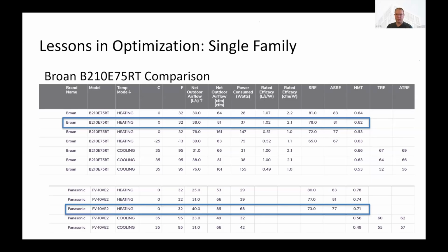Although there is a trade-off there. It has a little less heat or less moisture recovery than the Panasonic. So I just want to point out here, though, if you're optimizing a building based on an 81% or an 83%, and your efficiency is actually 77%, then you run into some trouble when going to actually design or certify the building.